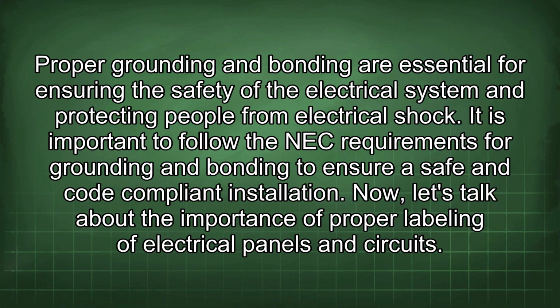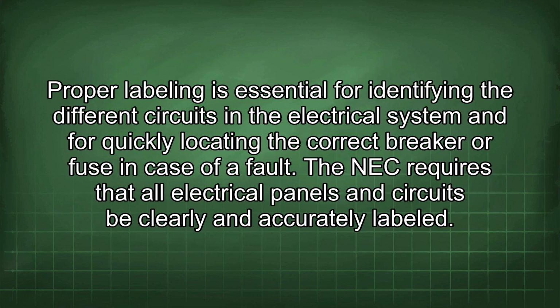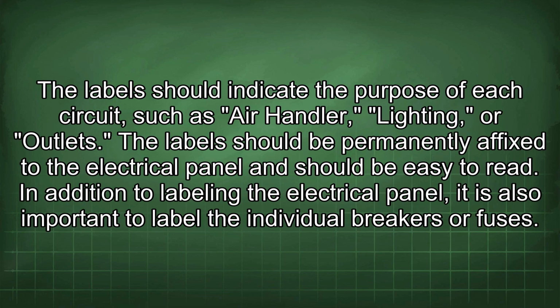Now let's talk about the importance of proper labeling of electrical panels and circuits. Proper labeling is essential for identifying the different circuits in the electrical system and for quickly locating the correct breaker or fuse in case of a fault. The NEC requires that all electrical panels and circuits be clearly and accurately labeled. The labels should indicate the purpose of each circuit, such as air handler, lighting, or outlets. The label should be permanently affixed to the electrical panel and should be easy to read.